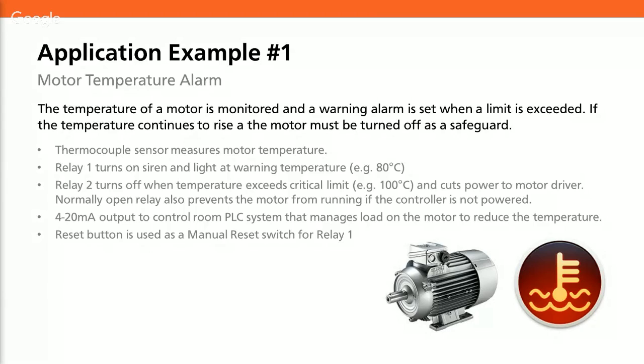We can also set up set points on the Merlin to react to the temperature of the motor and perform different control actions. So for example, we might be using a thermocouple sensor to measure the motor temperature, and then we can use the relay 1 on the Merlin as a trigger for a siren and a warning light when the temperature exceeds 80 degrees C. And then we can also use the second relay to cut power to the motor when the temperature exceeds a critical limit of 100 degrees C.